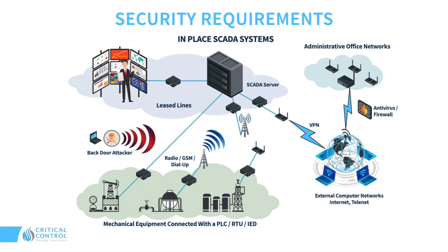Some people might be wary of trusting cloud-based software with all their data. How does the security on a SCADA system compare to that of a web SCADA system? Anything connected to the internet today is going to be a security concern. SCADA systems are just as susceptible as everything else. In the old days, if you had a system that wasn't properly set up, there were certain security flaws — for example, Modbus and DNP3, very common SCADA protocols, don't support authentication and encryption. So organizations had to look at how to separate that control system from their corporate system and control access to users required to interface with the SCADA system directly.